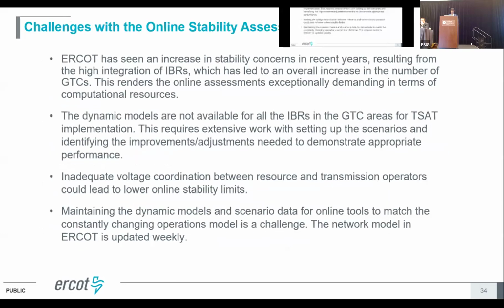The challenge with getting all of them onto the online system is that we are currently managing 24 GTCs, and for each one, if you want to calculate the stability margin, we have to do transfer analysis in TSAT. As you may know, TSAT is computationally intensive, it has to study the base case condition and push the transfer across the GTC further and further until it reaches the stability point, then send the limit back to the EMS system.